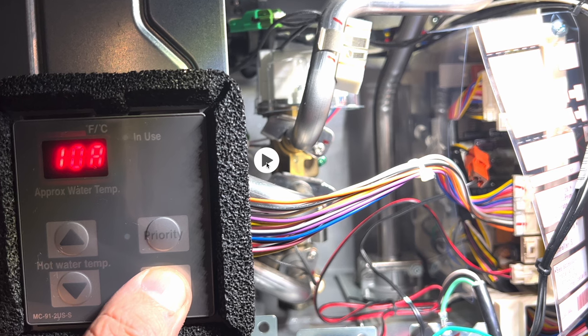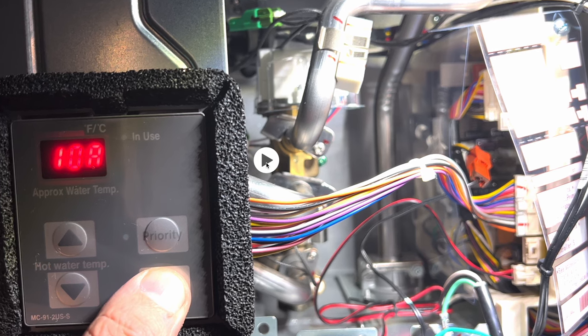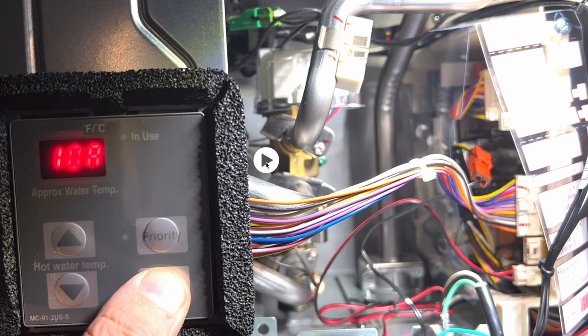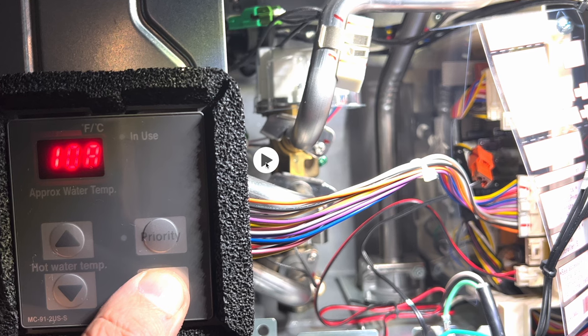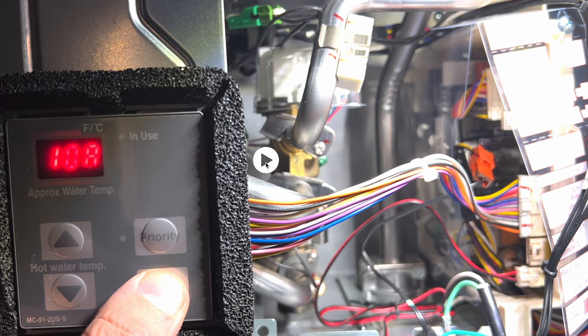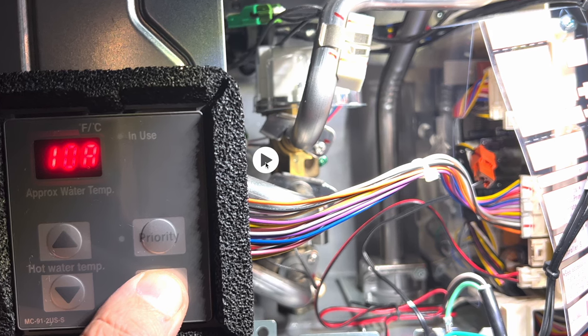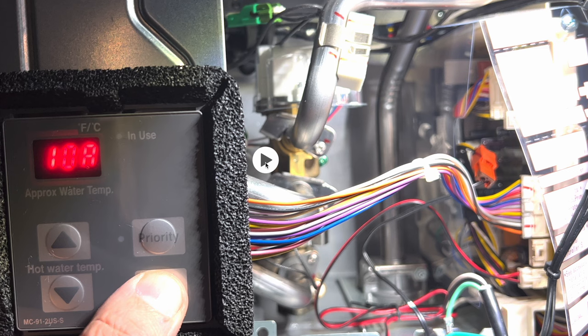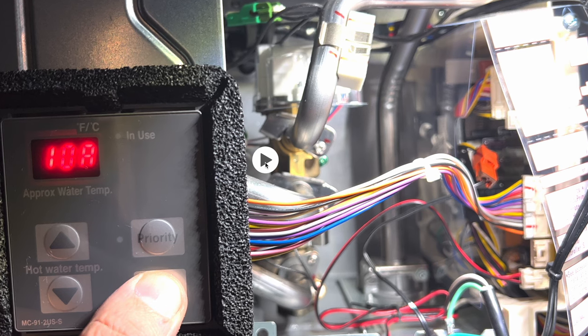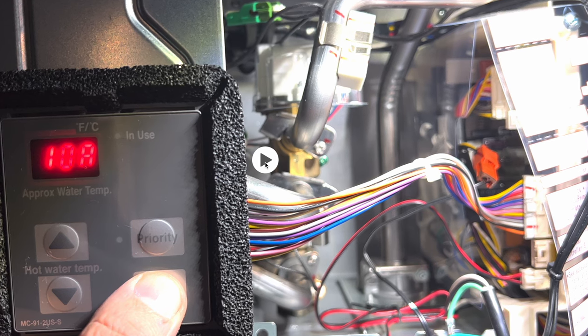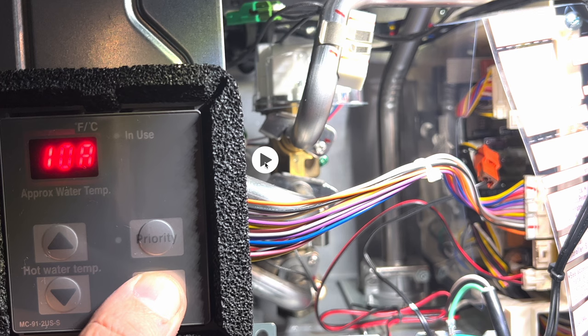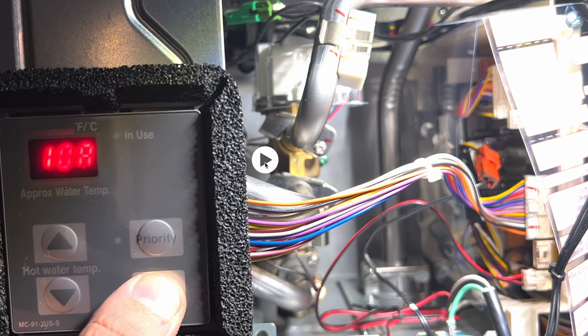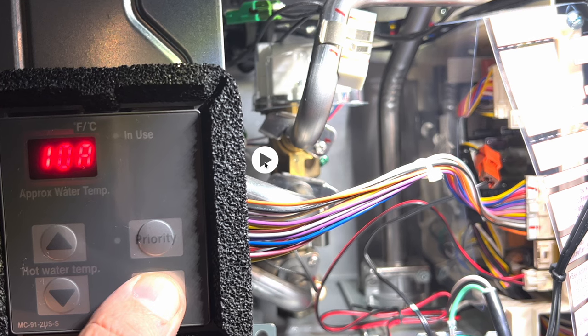Setting 10 is for the type of gas used. The default selection is A for natural gas. Selection B is for liquid propane. So if you are running propane, you will have to come and select B here. Keep in mind that depending on the water heater model you have, you might also need to take additional steps such as replacing the orifice for the gas manifold.